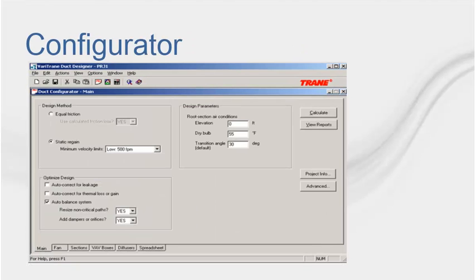The Duct Configurator helps you size the supply duct system, identify its critical path, and determine the static pressure and airflow required at the supply fan. If you choose, it can help you resize non-critical paths by identifying the fitting sizes and placement needed to balance the system. The other tabs at the bottom of the screen allow you to enter the details of your planned duct network.